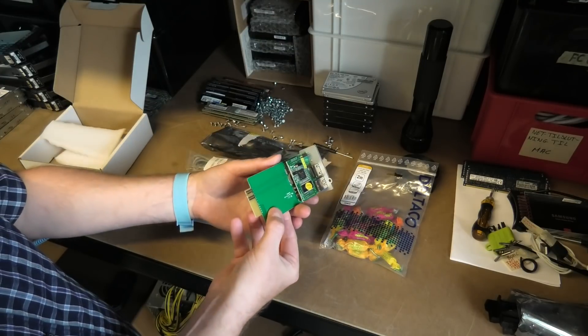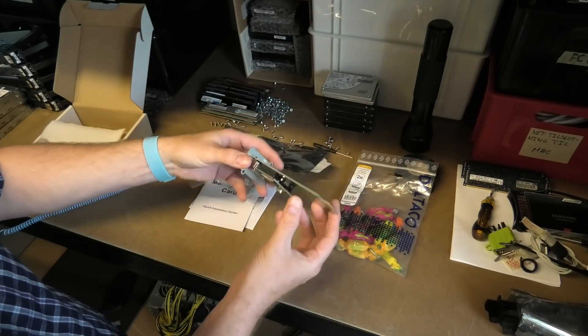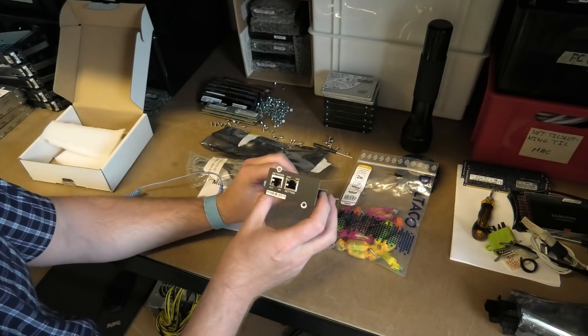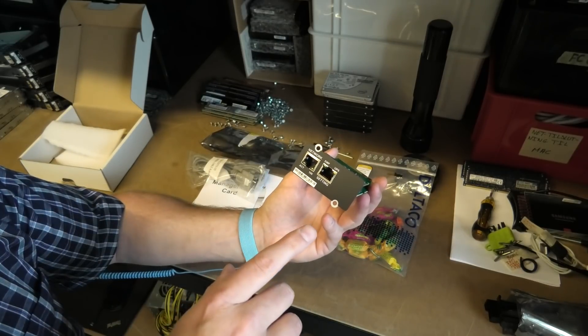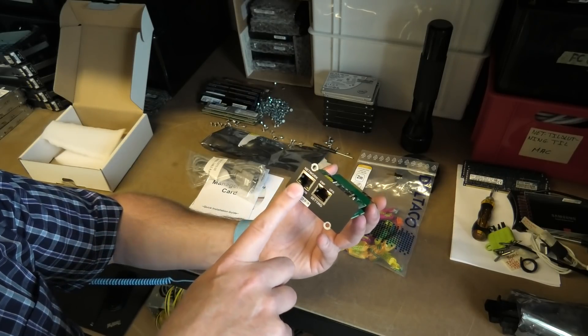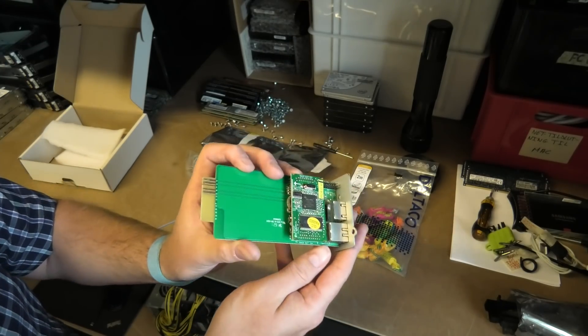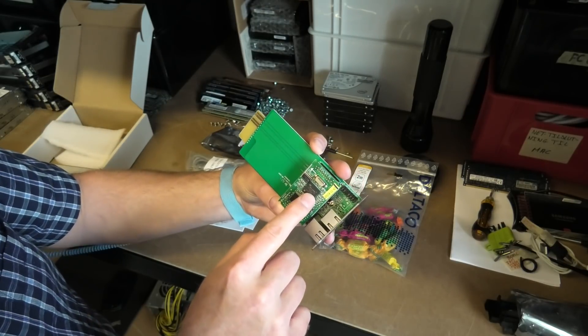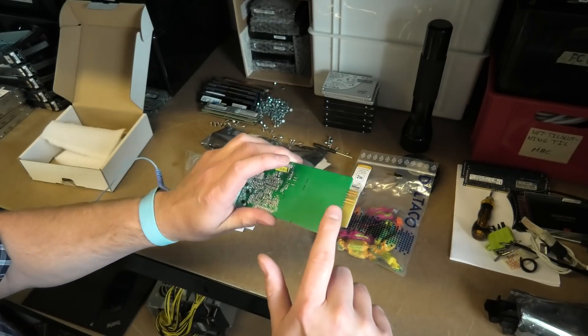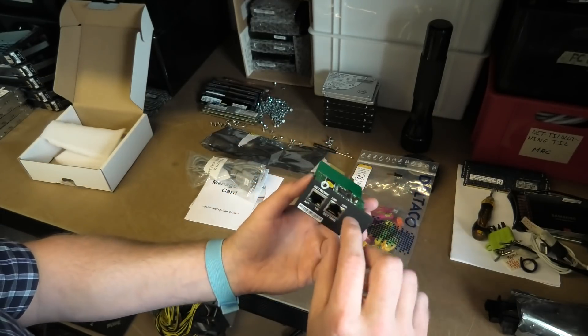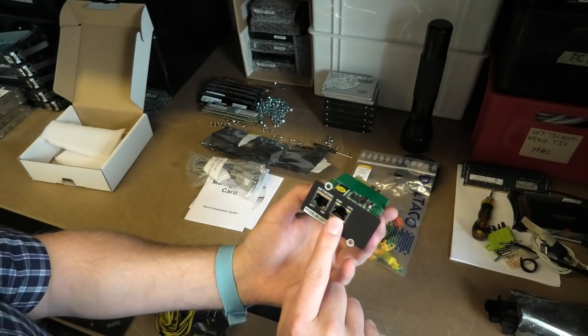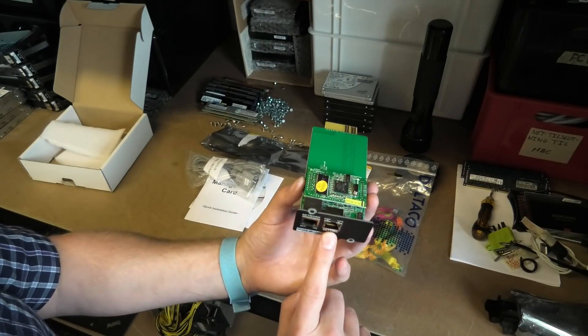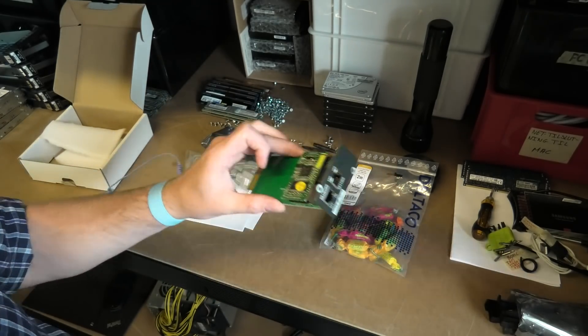I didn't know about that little board there. I hope this fits, but most likely it will. The UPS has management but currently there's only access from a serial connection or USB connection. With this thing you can connect it to your network. There is a tiny web server built in on this. There's a tiny ARM processor right there. This connects to the serial connection and some power in the UPS, converts that data into a web page. To manage this card I connect to this port here which is an RJ45 connection but it is really a serial connection.